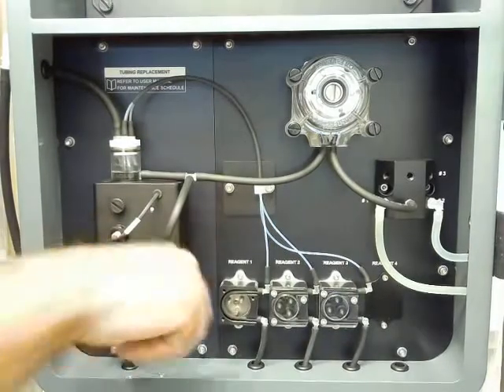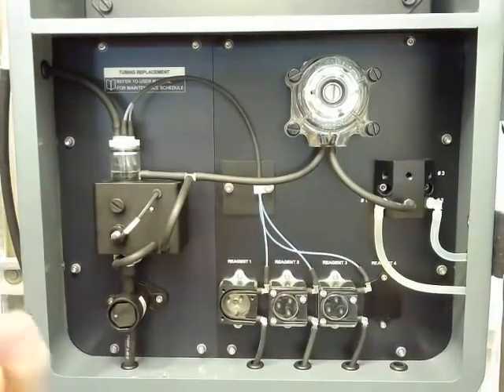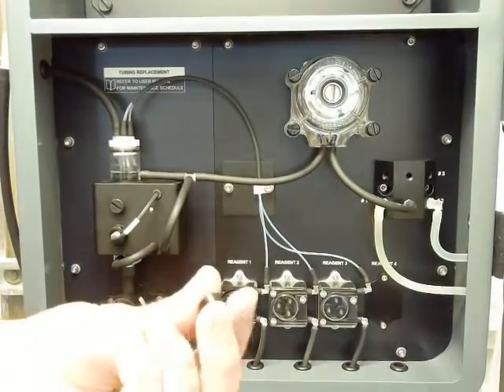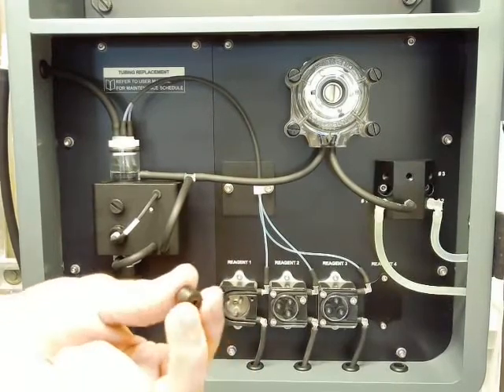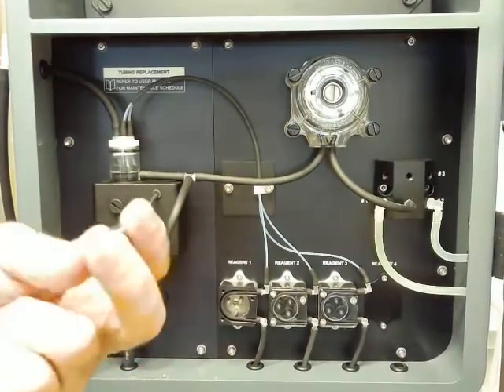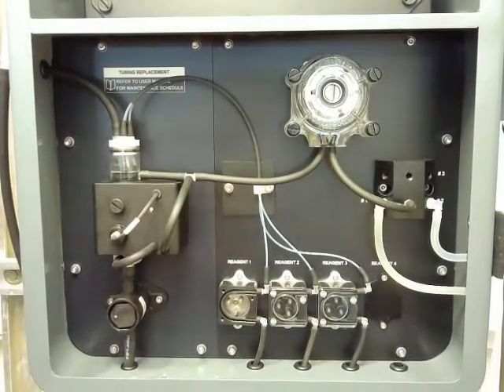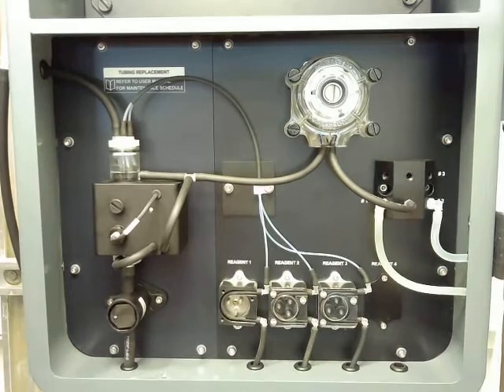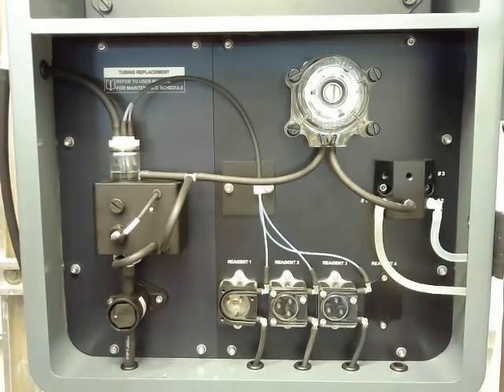And now we've got to get our pump rollers back in place. So your kit will also come with a replacement set of rollers. They're plastic, so they'll wear a little bit over time. Again, there's enough for once a year replacing these rollers. It's always a good idea to inspect them, but they shouldn't see any excessive wear until you get to about a year's worth of runtime.